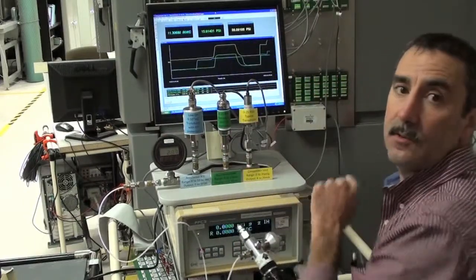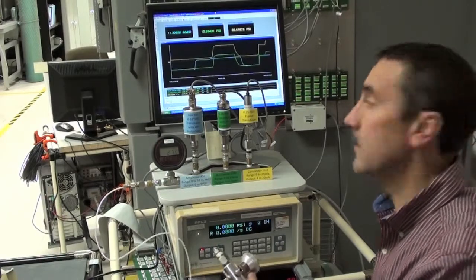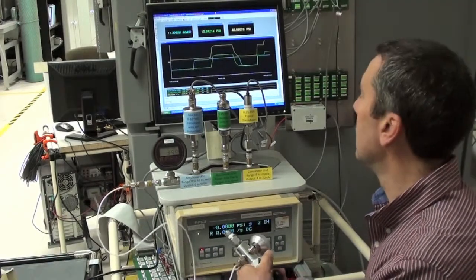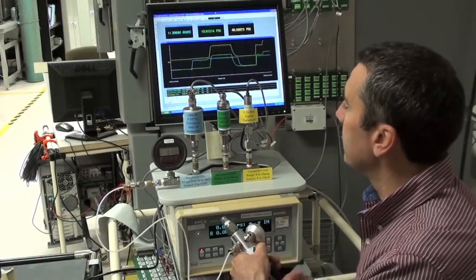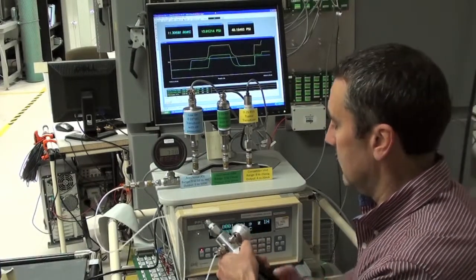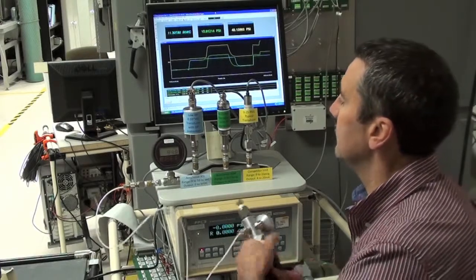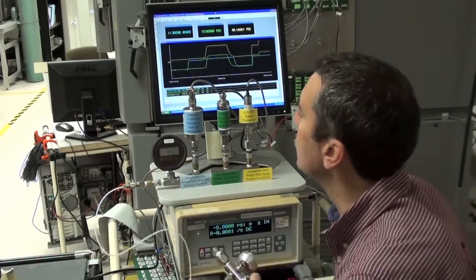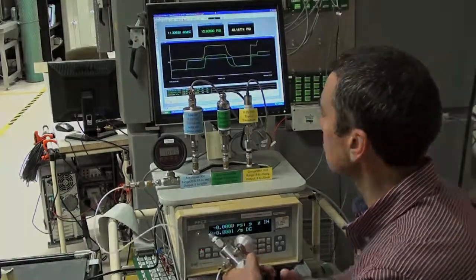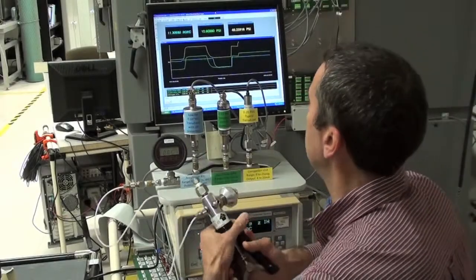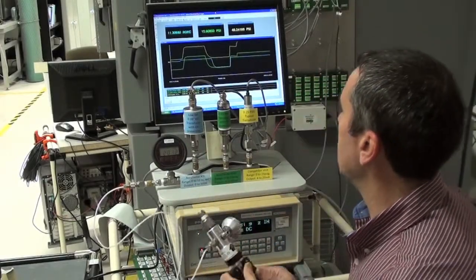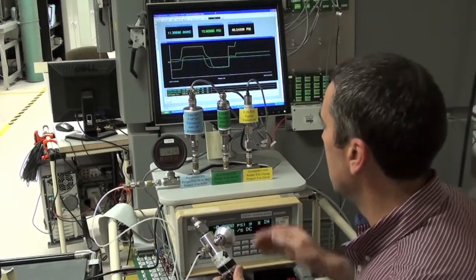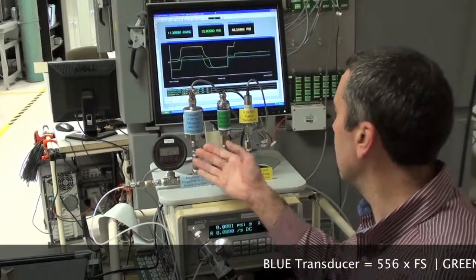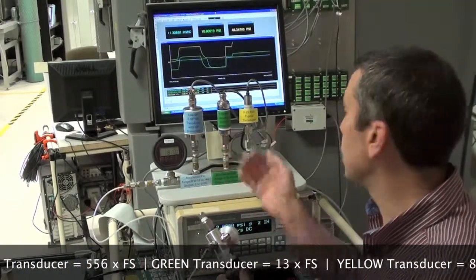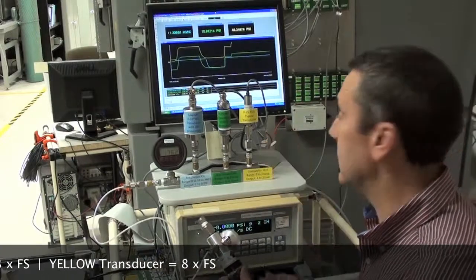And again, this one was falsely recording pressure because it had already been overpressured in a previous test. So I'm going to bring this manifold pressure as high as I can get it within the limits of this digital pressure gauge, which is basically 200 psi range. So I'm at 200 psi. All of these units are now highly overpressured. This one over 500 times its full-scale rating. This one over 13 times its full-scale rating. This one about eight times its full-scale rating.